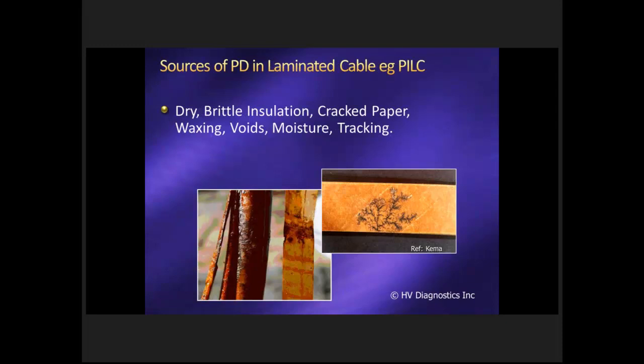PD can also occur in paper lead cables, so you can see over there, in the paper lead cable that's got PD activity that's been present. Both on the left-hand side, and if you look at a paper wafer, you can see on the right-hand side a small, it's like a tree that's taken place due to partial discharge activity inside the paper cable. One thing about paper cable, it does have a tremendous ability to actually quench or self-heal itself when it comes to PD, which doesn't tend to be a property of cables like, for example, XLPE.